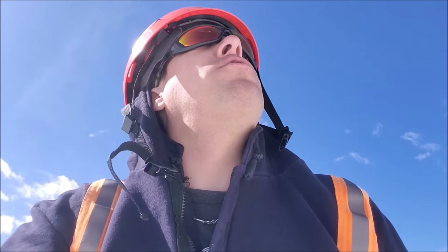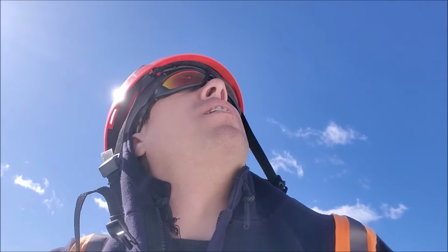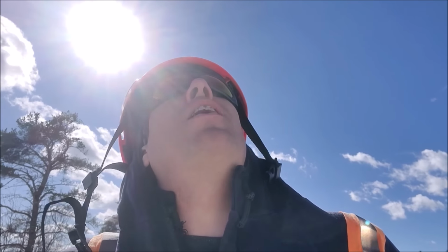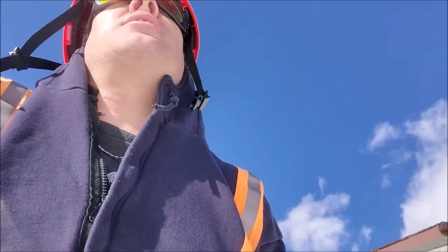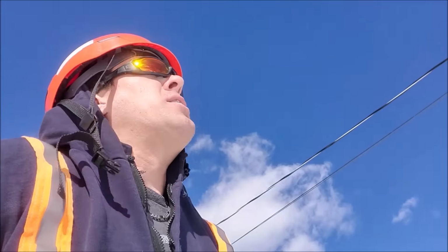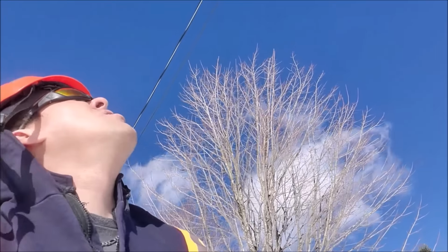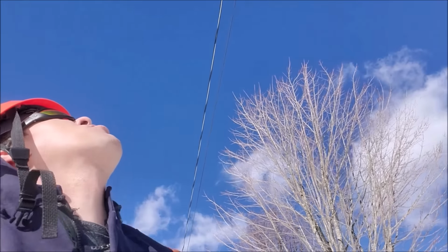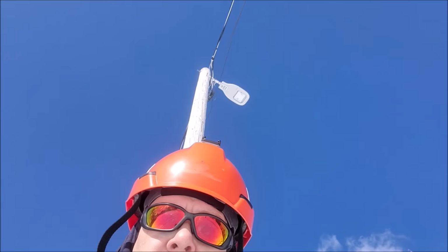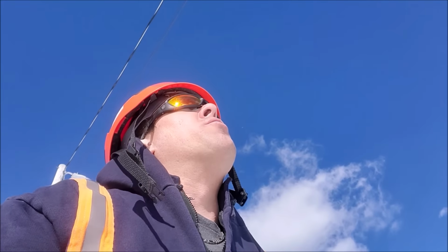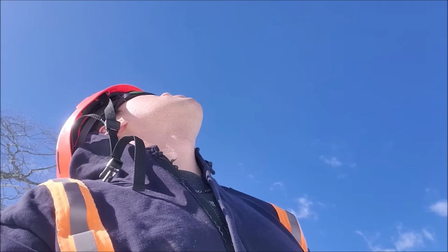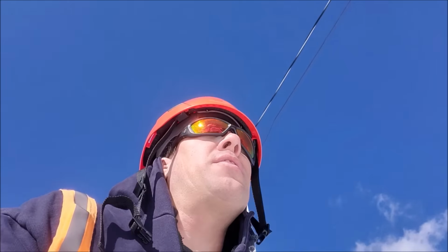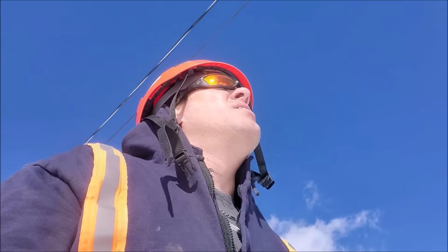We're going to take a look on the roof. We've got 4/0 copper to 1/0. There's no visual oxidization. Take a walk down the line. The neutral is straight through on this pole. There's a couple of connections feeding that light on it, but the neutral itself is not cut, so we know there's no issue there. And the neutral is straight through on that pole as well.